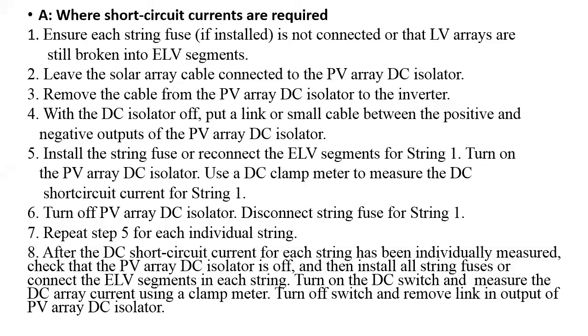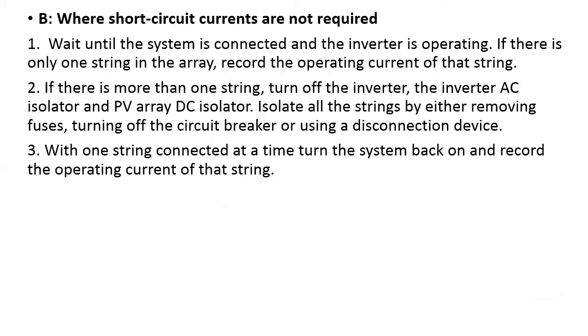This is the simple procedure they follow for checking the short circuit, and this is for one string. Similarly, this has to be repeated for each and every string, by isolating the remaining PV arrays with the DC isolator. Similarly, there is a procedure for measuring where short circuit currents are not required. For that, they wait until the system is connected.